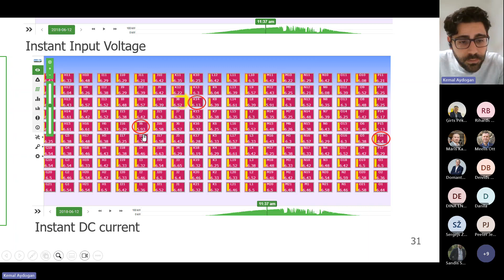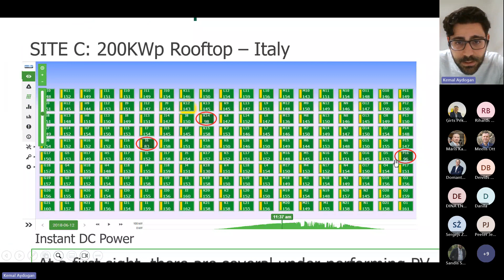As you can see, these PV modules are actually producing less. Then you zoom in and understand that they have a diode issue, because you have voltage values and current values, so you have everything. Actually, you can't understand this from the current values alone, because the current value is almost the same as the other string members. In this string, all of them are almost producing the same in terms of current, but in reality individual performance is less. So you can only understand this if you check module level voltage values here.